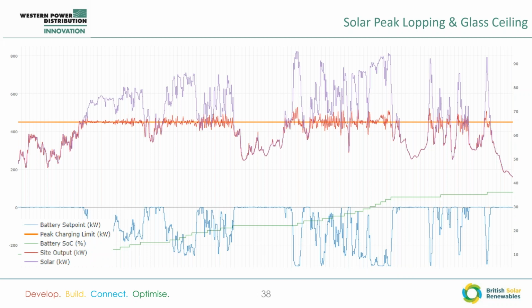This is demonstrating the battery in peak lopping mode. We set the peak lop at 450, which is the orange line, 450 kilowatts. The orange line running from left to right there. And then the purple is the generation of the solar. So every time the purple goes over the line, the red line, which is the overall site output seen by the grid, should stay at 450 kilowatts. I would say that the battery works at this fairly well.